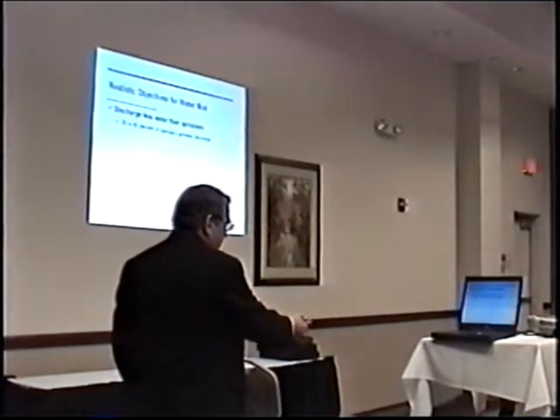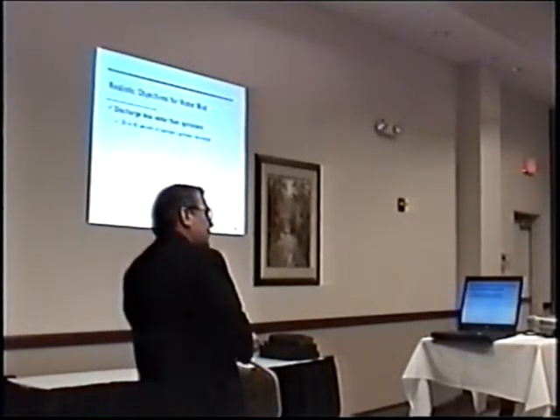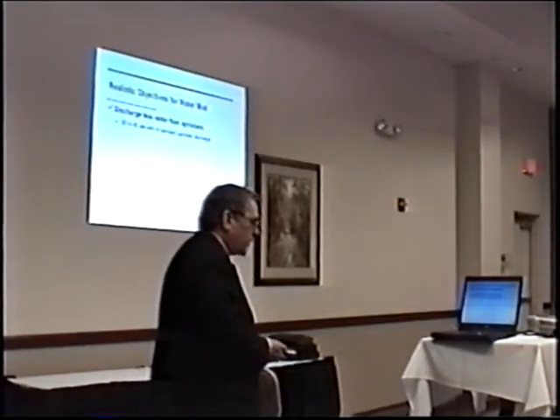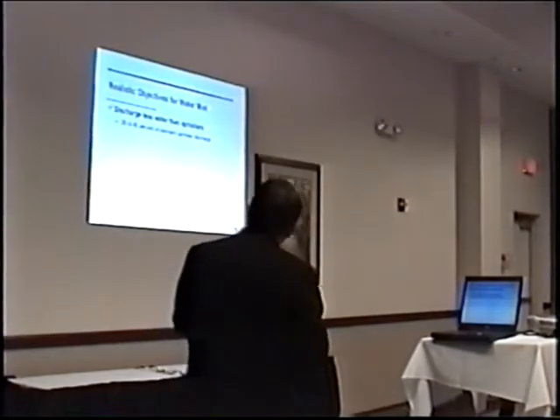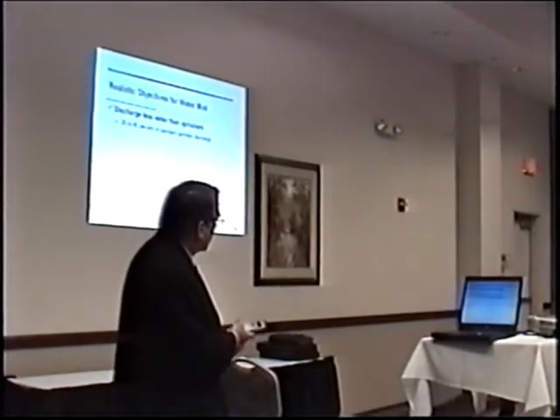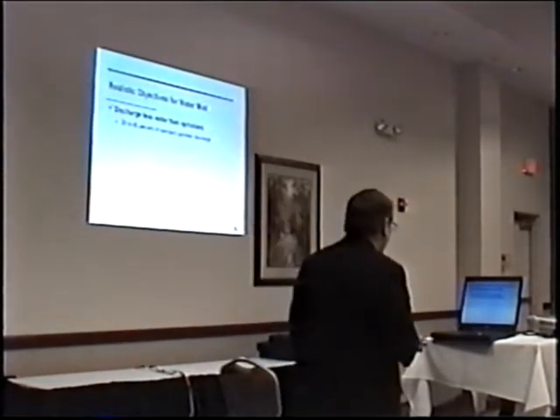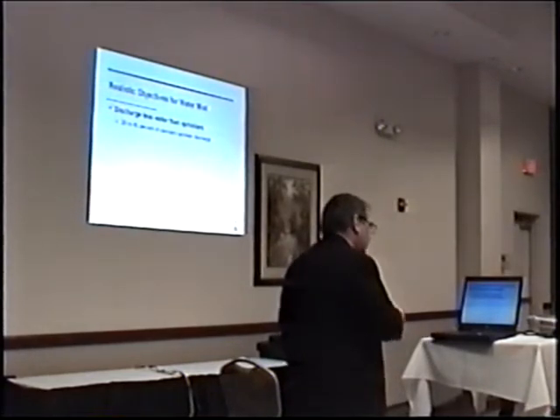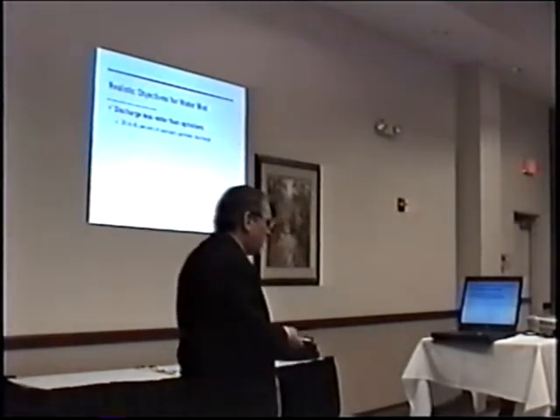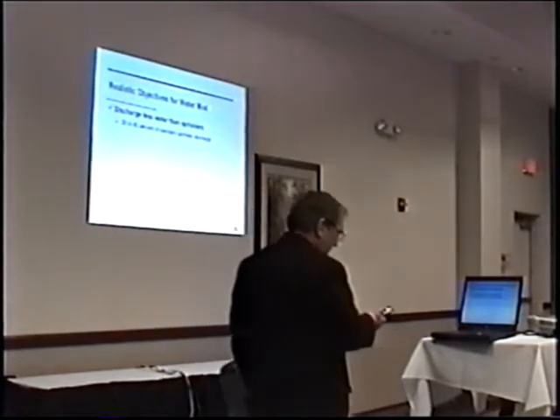Seems good to do one at a time. Let's look at the claim that water mist systems are a good thing for heritage buildings because they discharge less water than sprinklers. And we know water runs down stairways and fills basements and soaks construction materials, so it'd be nice to use less of it. Well, it is true that in general, water mist systems achieve their suppression objective using perhaps 20 to 40% of the discharge that we get from standard sprinkler systems. So that's a good thing.